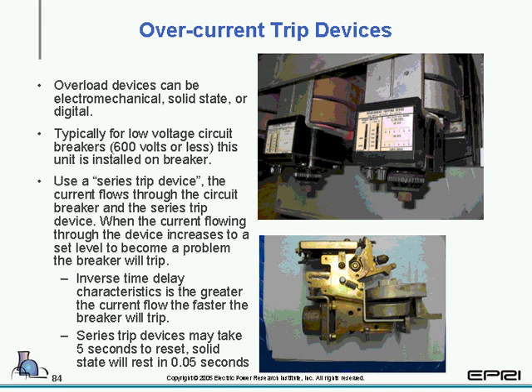Most commonly found on lower voltage breakers are overcurrent trip devices. These particular ones, we're going to take a look at three different types. The first one we're going to take a look at is the electromechanical, then the solid state and the digital. Typically of a low voltage circuit breaker, 600 volts or less, this unit is installed in the breaker and is used in series with the trip device.